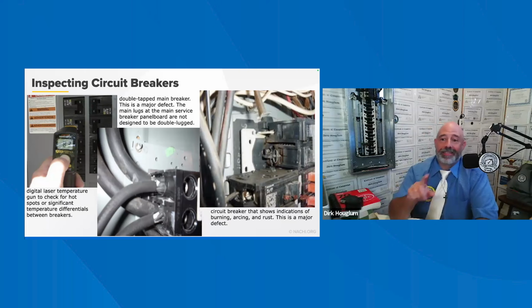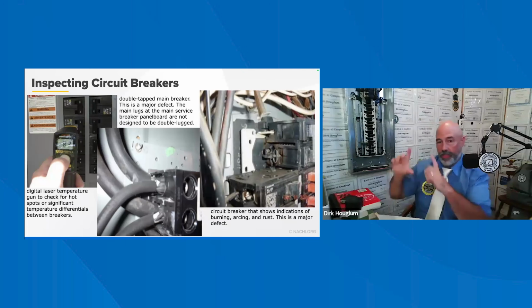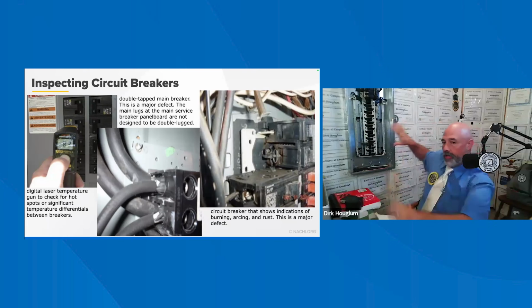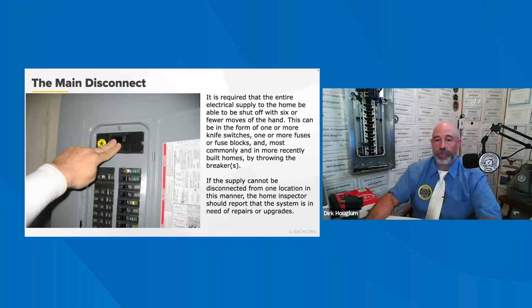Note, the GFCI and AFCI breakers will always be about 5 to 10 degrees hotter than standard breakers due to their internal circuit board. So when I do my thermal readings, I always take a thermal reading of it, and you can actually see them a lot hotter. Now, all electrical systems require a means of disconnect.